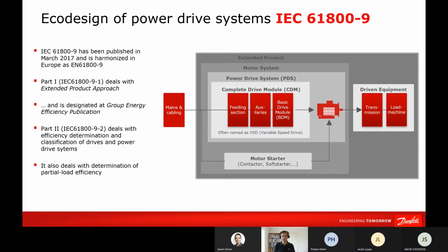And it also deals with determination of part load efficiency, because if we run variable speed, then of course it's not only important to know what's the efficiency when we run full speed, it's also important to know what's the efficiency when we regulate the speed and reduce the speed. And these are these partial load points.